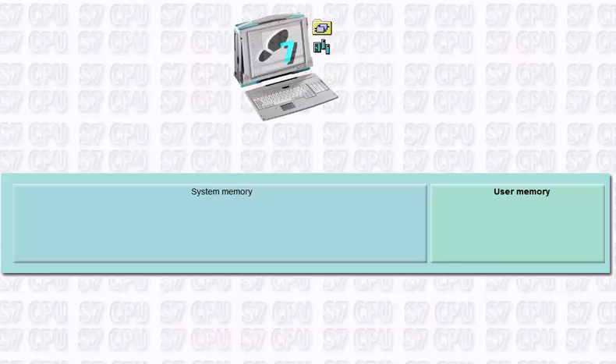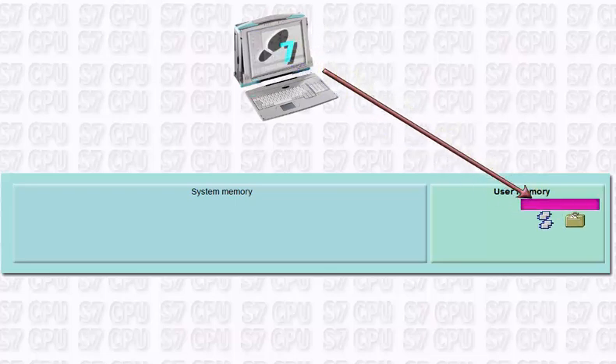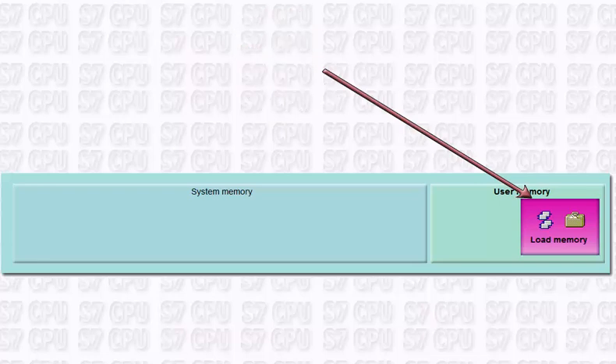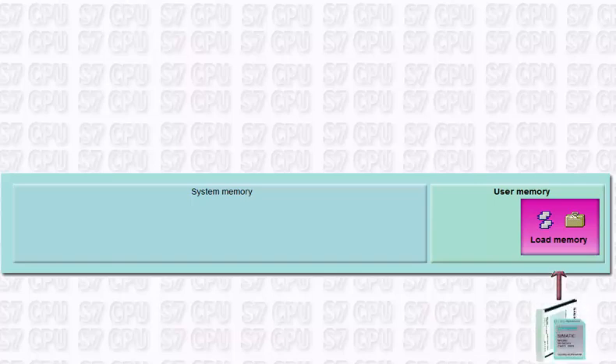In the operating mode Stop, a download of the user program and the configuration parameters of the hardware into the load memory of the CPU is triggered. The load memory is designed as memory integrated into the CPU or as plug-in memory card.